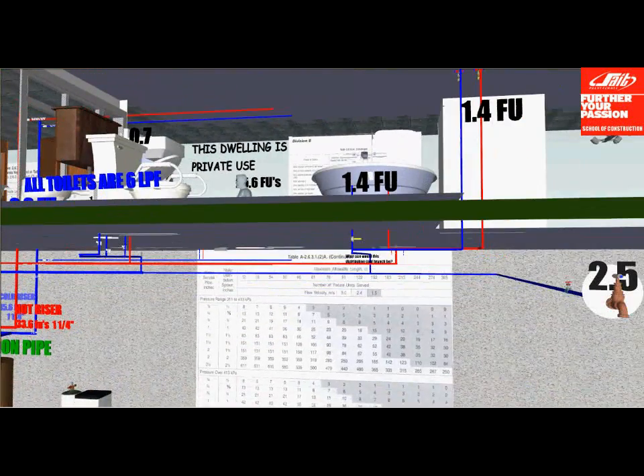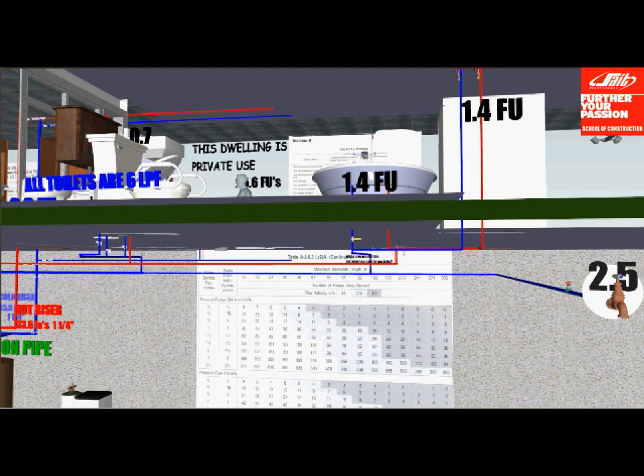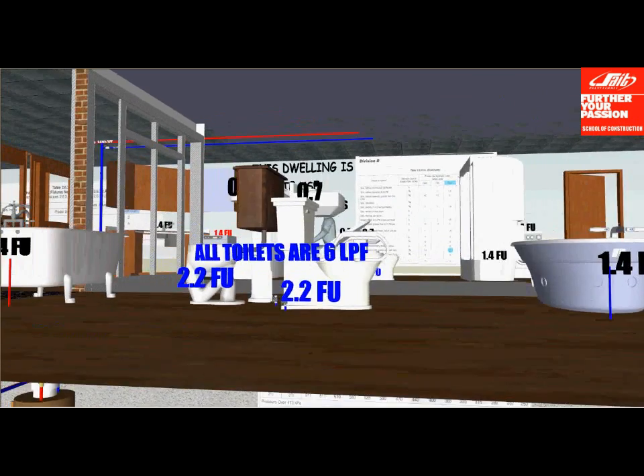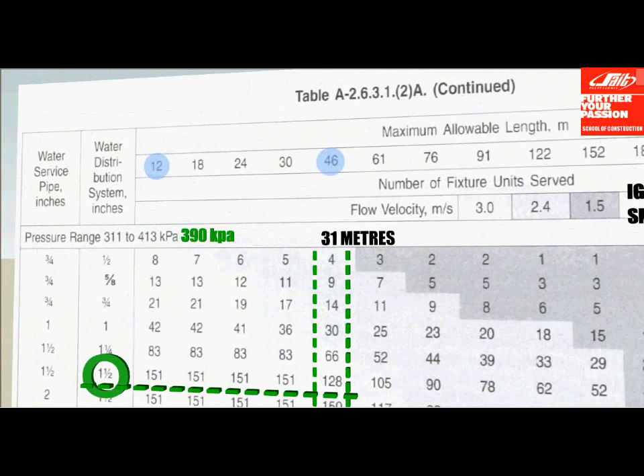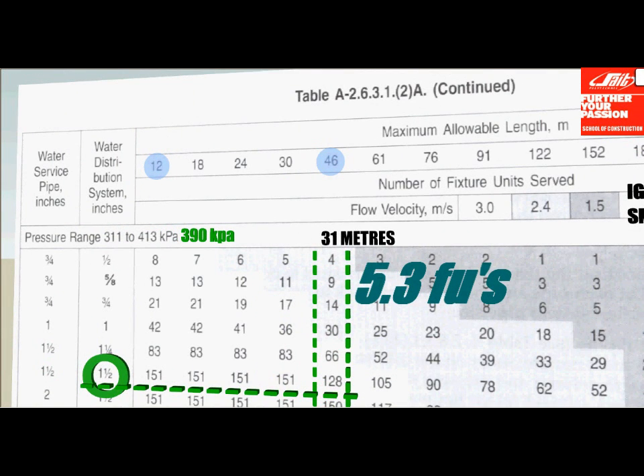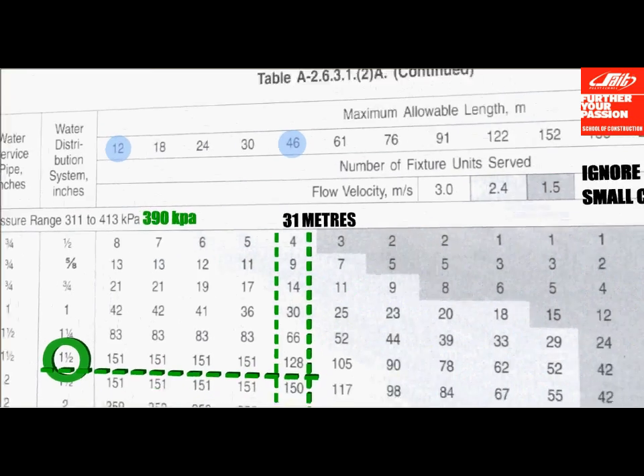As the cold water distribution branch is sized the same as the hot distribution branch, let's now size the cold branch to the right of the bathtub and clothes washer, including the hose bib. The bathtub and the clothes washer are both worth 1.4 fixture units each, plus the hose bib, which is also worth 2.5 fixture units, for a grand total of 5.3 fixture units. As you can see, we have to go to the number 9 as we have 5.3 fixture units, and this will give us a cold branch of 5/8 of an inch.